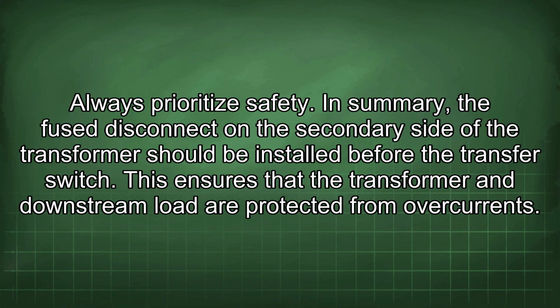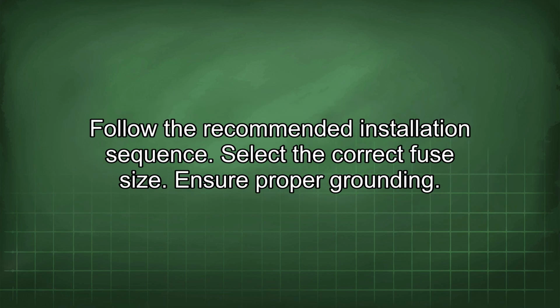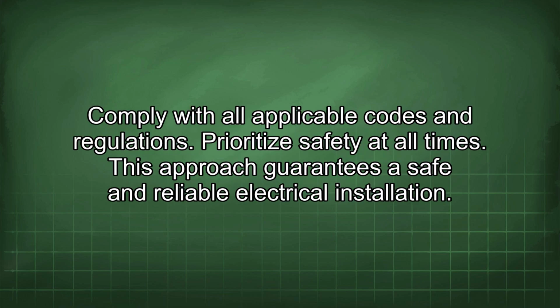In summary, the fuse disconnect on the secondary side of the transformer should be installed before the transfer switch. This ensures that the transformer and downstream load are protected from overcurrents. Follow the recommended installation sequence. Select the correct fuse size. Ensure proper grounding. Comply with all applicable codes and regulations. Prioritize safety at all times. This approach guarantees a safe and reliable electrical installation.